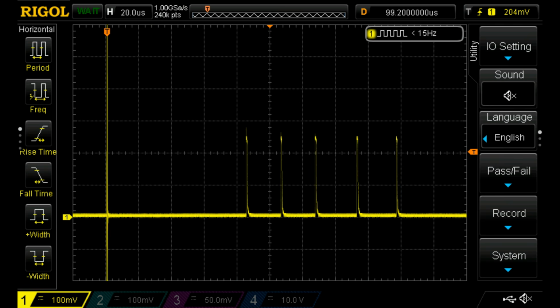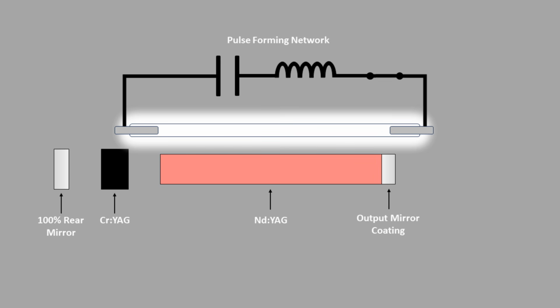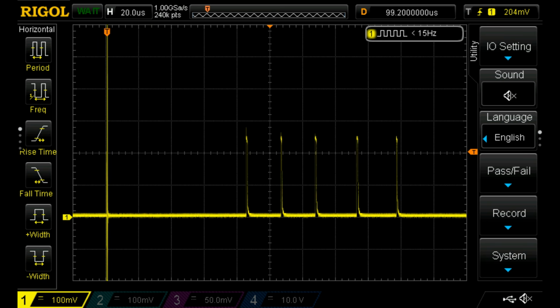If you recall, the duration of the pulse forming network is set such that the flash lamp will be lit for about 200 microseconds, and those 5 pulses occur within that time frame. So what happens is, the YAG rod is pumped by the flash lamp, the Q switch eventually reaches threshold and fires, but the rod is still illuminated, and so it pumps the rod right back up to threshold again, and the cycle repeats. I suppose if I was to redesign the pulse forming network and get the flash to be maybe under 100 microseconds, we could get a single giant pulse out of this. I'm not sure how well the lamp would cope though.